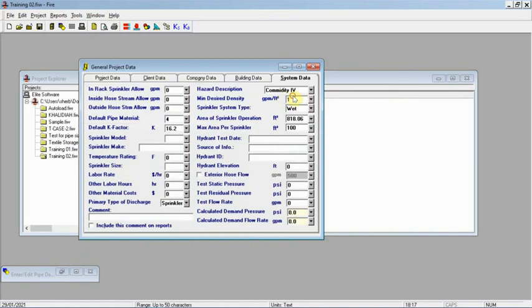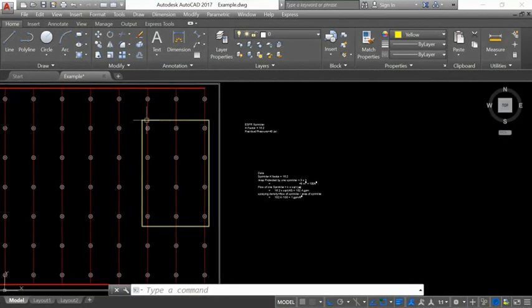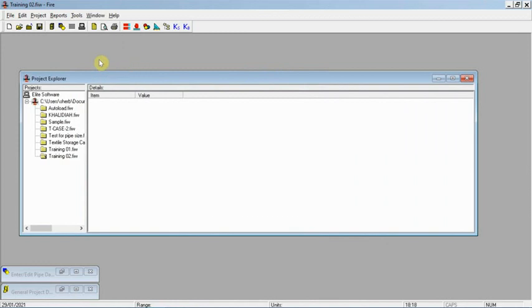Once you calculate it, enter it directly into the program. Choose the sprinkler system type as wet, enter the area of sprinkler operation — calculate the most remote area and enter it into the program — and set the maximum area per sprinkler as 100 square feet. This finishes the general project data.